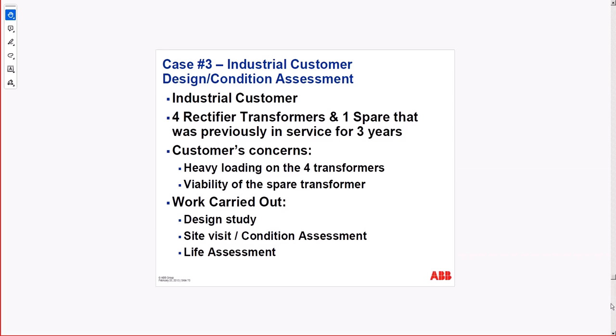Or if not, at least you have the transformer with a few turns of the insulation increasing in thickness, low capacity cable that connects, and so on. So there are techniques to have lower dissipation of the heat and stress from the THD, total harmonic distortion, including the shape of the copper. Not necessarily will it be the conductor that we know.